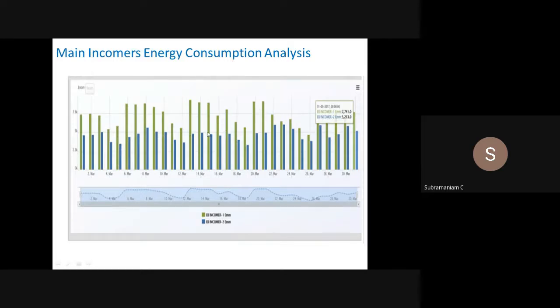This is incomer 1, incomer 2. Now, if I analyze this over 1 month, which means incomer 1 is consuming more, incomer 2 is consuming less, the load is less on that. Is there a reason for that? Is there a problem with incomer 2? All that kind of analysis can happen from BMS. And this is your LT energy consumption for all your different things. Chiller panel, kitchen, fire panel, utility panel, we can get that value.